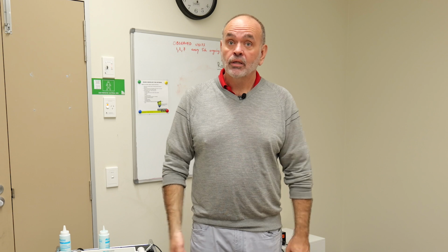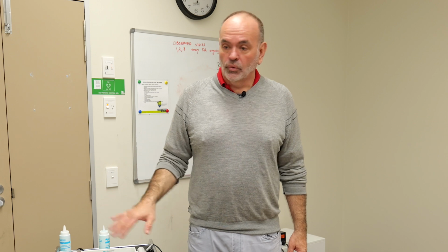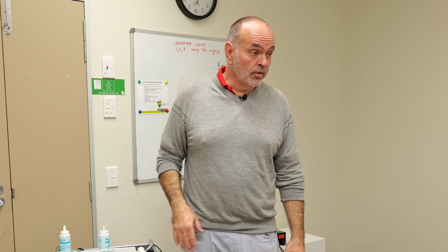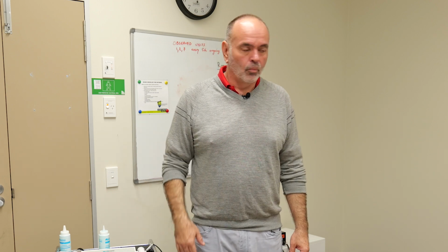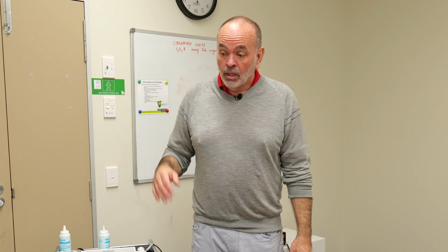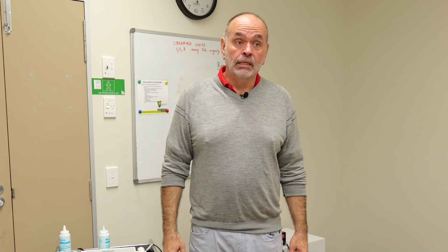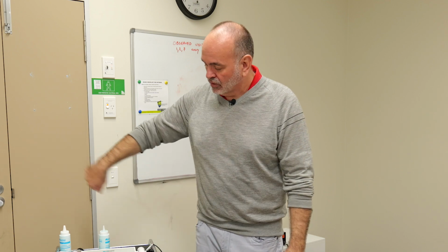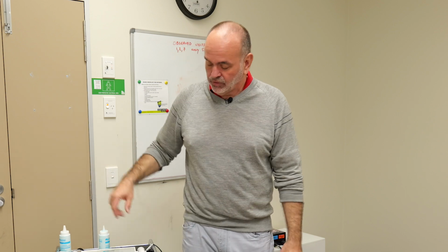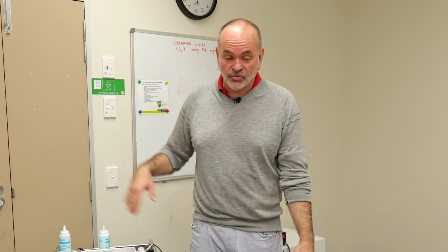Heat can be therapeutic, but this machine can very quickly get hot enough to cause burns. So you have to be mindful of that. So in terms of power setting, we're always quite conservative. We never go beyond that 1.5 watts per centimeter squared. We can control the amount of heat in a few different ways. One is by controlling the intensity of the sound that's coming out in watts per centimeter squared.